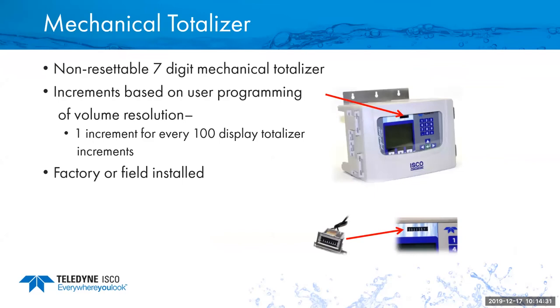The mechanical totalizer is an option that could be either added at the factory or in the field. It is the ability to add a non-resettable totalizer. So it's 7 digits, so it just looks like an odometer that is set in there that measures the flow and increments itself by 1 every 100, say 100 gallons or 100 million gallons or whatever your setup is on the display. So it'll kick over 1 increment every 100. So it's easy to program and install, just plugs into the circuit board, so it could be done in the field at a later time if necessary.